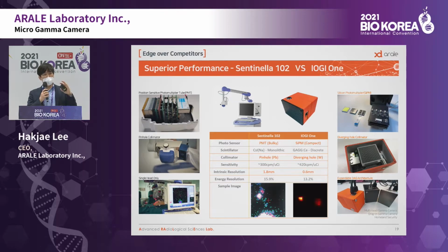Compared to Onco Vision, the conventional product, which used a vacuum, we have the light sensor based on semiconductor technologies. And the lens is a collimator in the gamma camera. Usually it used the pinhole collimator, but we have a diverging collimator using tungsten, so it has very high performance of shielding, lead shielding. Now we have a 0.6 millimeter resolution.